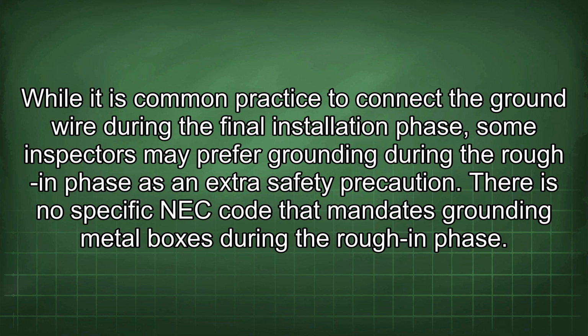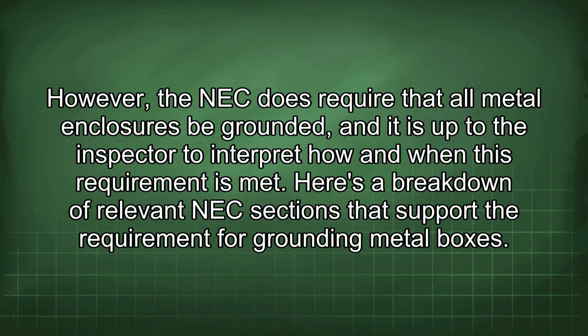There is no specific NEC code that mandates grounding metal boxes during the rough-in phase. However, the NEC does require that all metal enclosures be grounded, and it is up to the inspector to interpret how and when this requirement is met. Here is a breakdown of relevant NEC sections that support the requirement for grounding metal boxes.